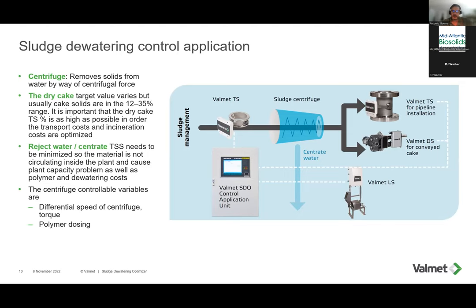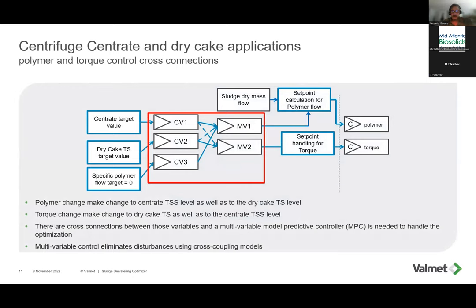Then you have two outlet streams. One is a cake coming out, so that is the thicker sludge that's been dewatered. And then you have the centrate water, which is basically the waste stream, which also contains concentrations of solids, which typically would have to be reprocessed all the way upstream. So those are the various input and output streams in a typical dewatering centrifuge. There are controlled variables, typically polymer dosing and differential speed of the centrifuge or torque, which are the two critical variables when you're managing a dewatering centrifuge. What this slide tries to show is that there is interaction between all these variables.